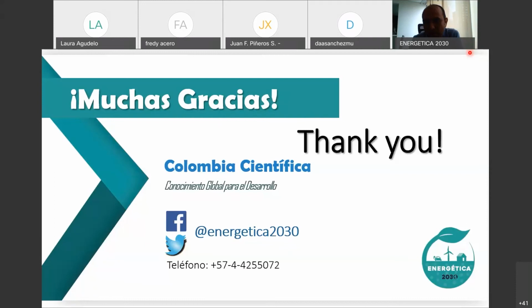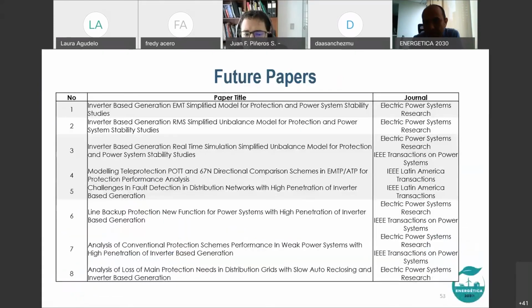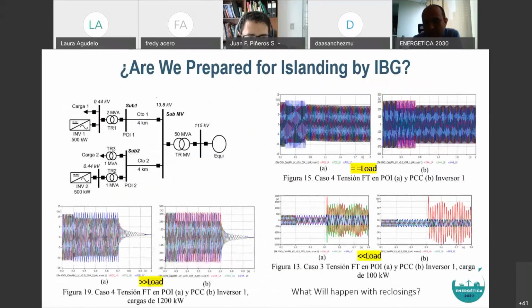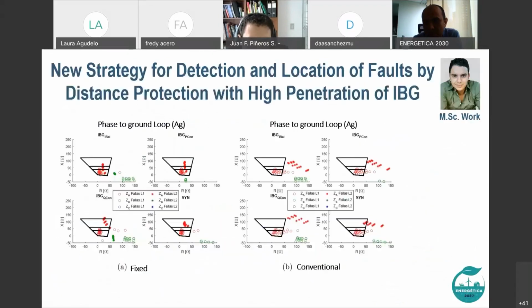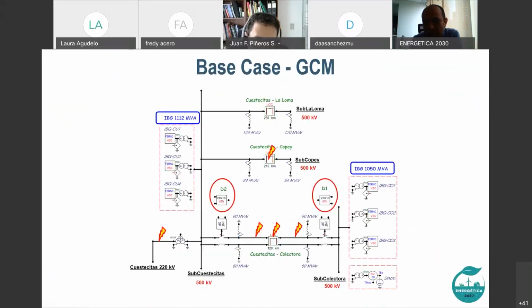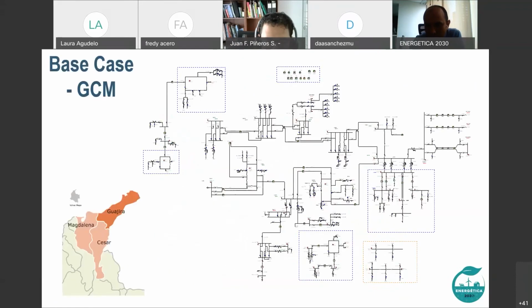Yeah, if you want, David, we can go back a little bit so that we can show the total network. But in general, we were modeling the Cuestecitas substation and all the substations around, and we were modeling the inverter-based generation there. Here is the zoom we have of this substation, but in the slide before, as I was presenting, you can see the whole network. Because of the simulation time, we were cutting and creating a network reduction in Santa Marta substation. I will request control here to point exactly at that point. Here, as you can see, we were creating a network equivalent using the DIgSILENT network reduction tools, and we were connecting the equivalent in general.